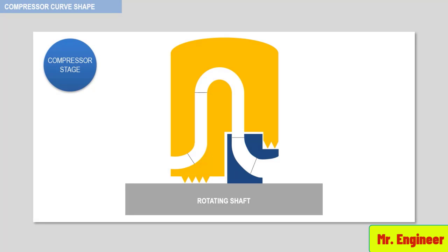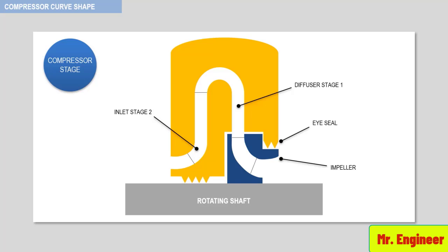A compressor stage is defined as one impeller, the stationary inlet passage, the discharge passage known as the diffuser as highlighted here, and the seals — namely the eye labyrinth seal and the shaft labyrinth seal.